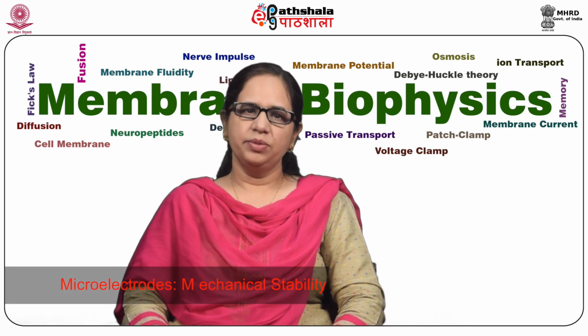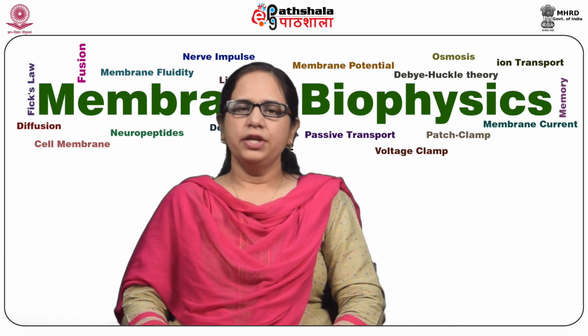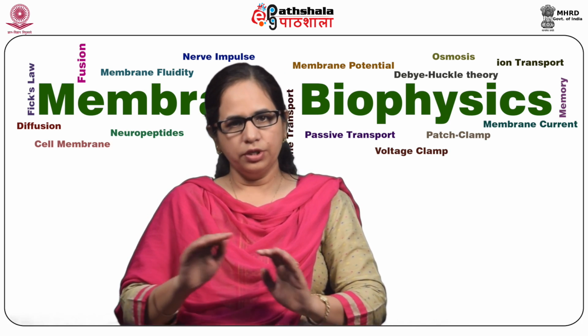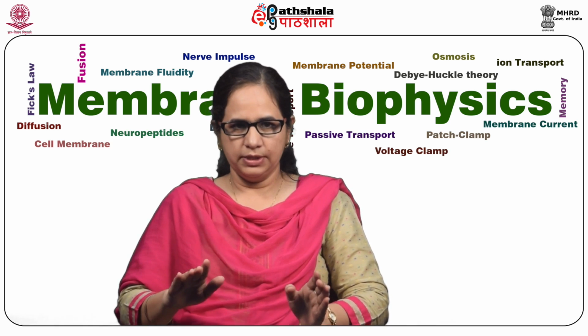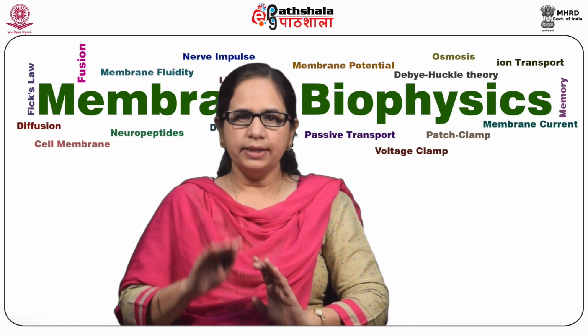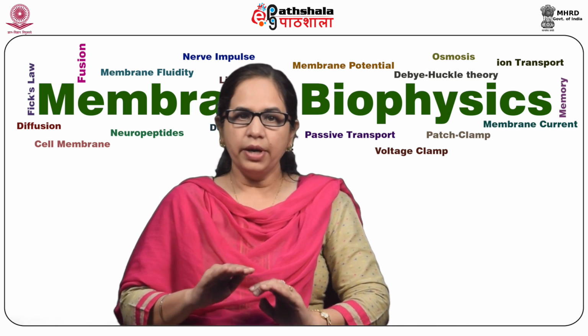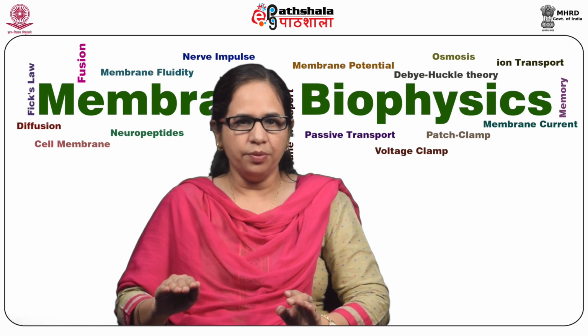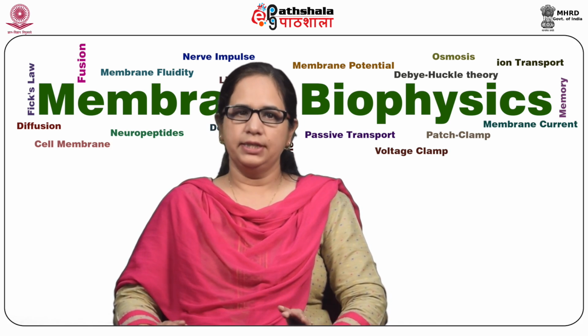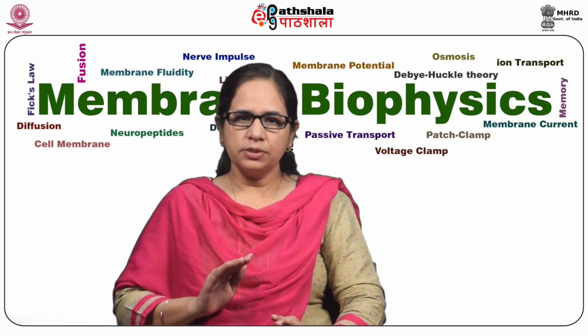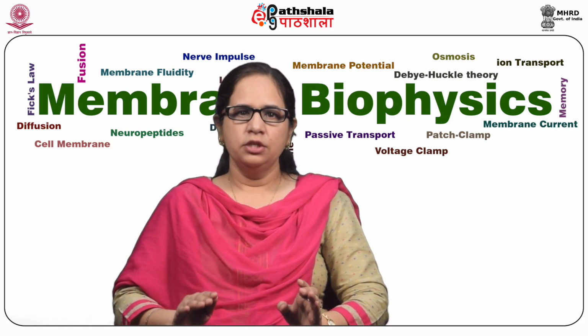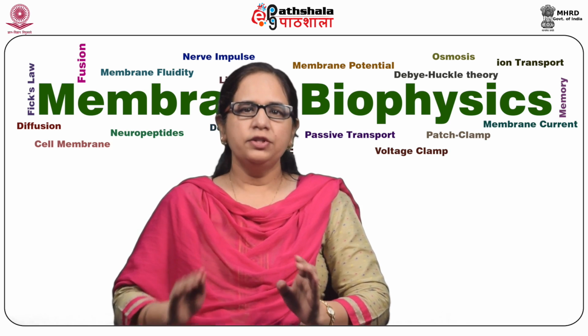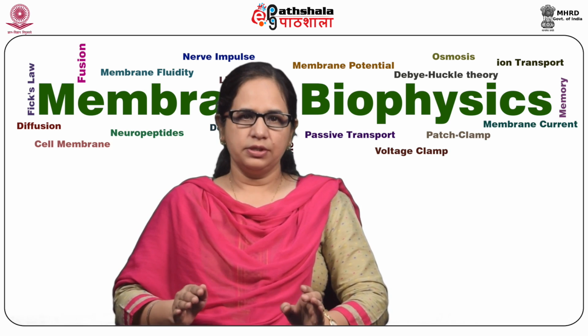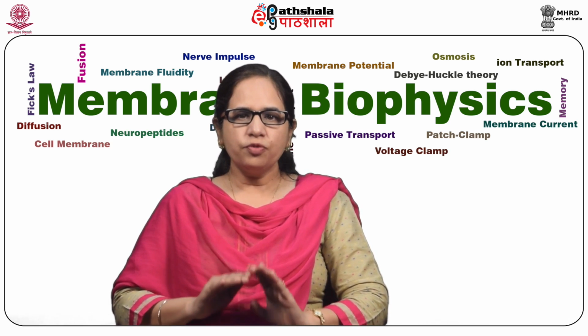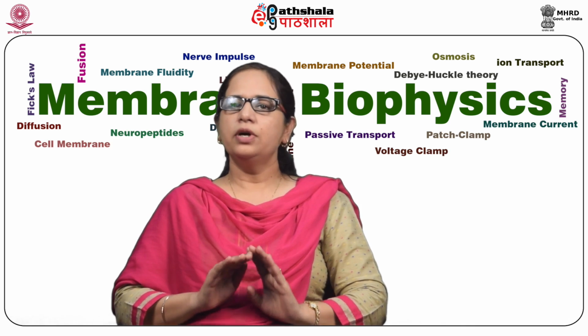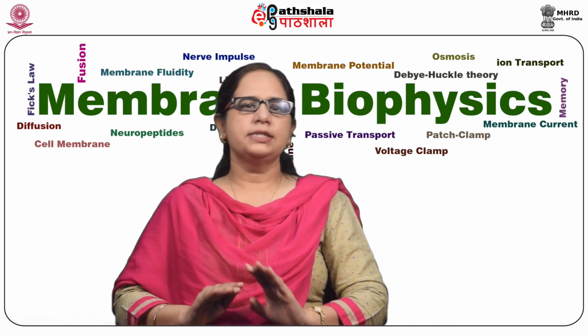Microelectrodes, mechanical stability. Mechanical stability is very important when you advance the microelectrode into the cell or on the surface of the cell. The interaction between microelectrode and the cell needs to be stable on a submicron scale to avoid damage to the cell membrane and consequent excess current leakage. There are two symptoms of the mechanical problems: slow drift of the microelectrode tip with respect to the cell and faster vibrations. Micromanipulators should provide precision of movement of less than 1 micron with stability in the same range.